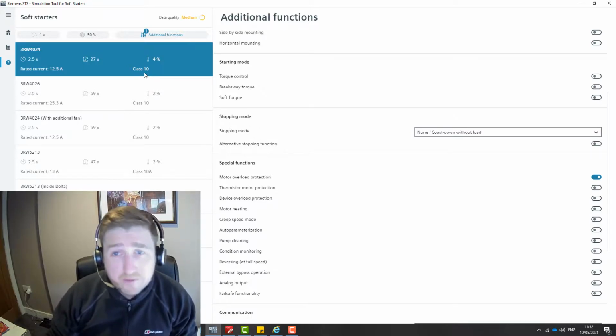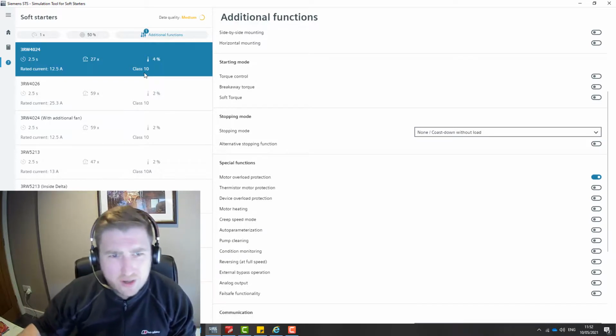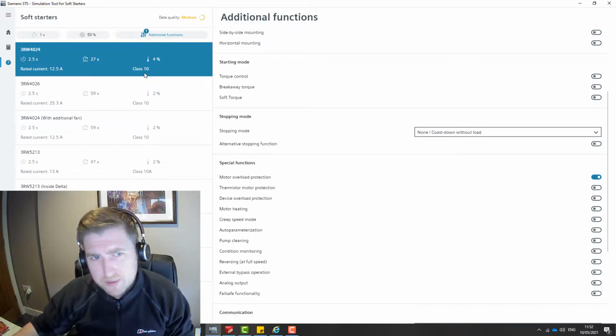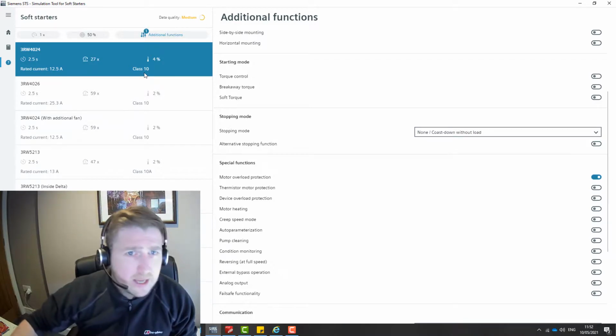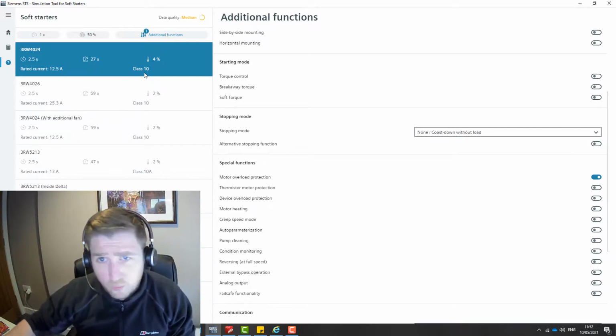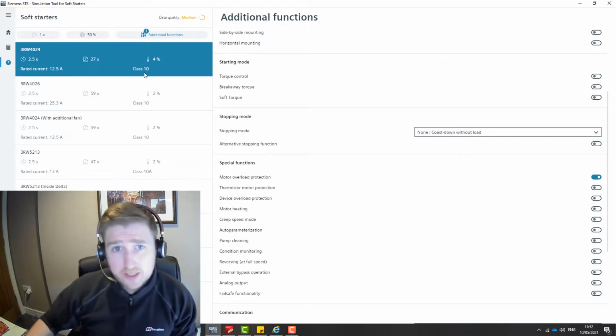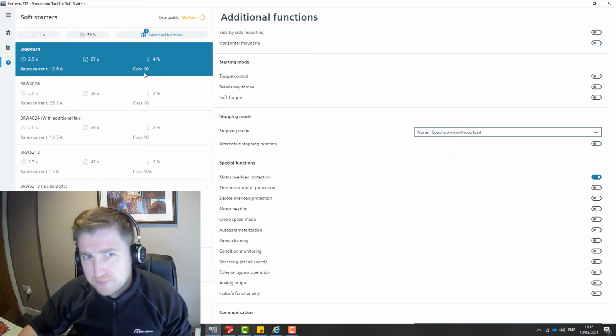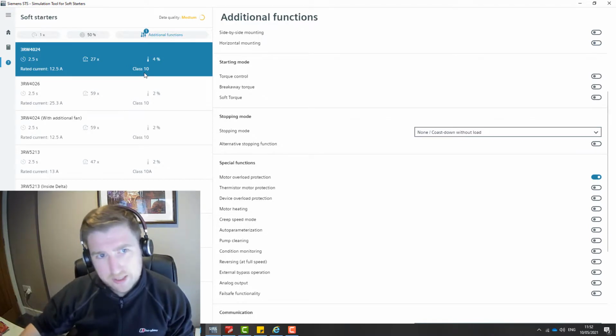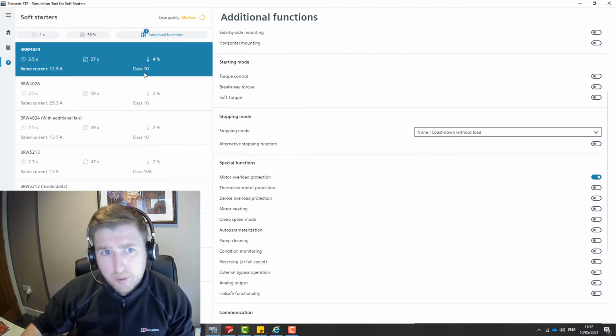The ramp down function doesn't actually cause any particular problems to the motor, so that one's not been included, because that function will work regardless of what you set it to, because all you're doing is removing the control voltage and then it will just coast down naturally to 0 RPM. It will try and regulate it dependent on what you set that ramp down time to, but it's not going to cause any issues with the process of starting and stopping, so that's why it's not being included.